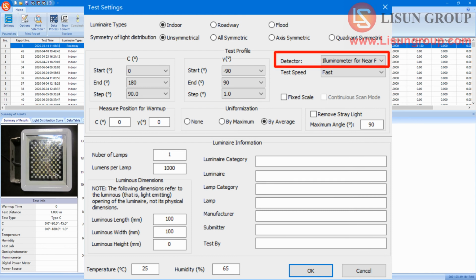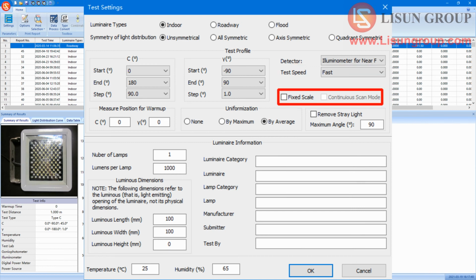Choose the correct photo detector that you use if you have more than one photo detector. Choose the test speed. Usually, normal speed can be used. Scale is not important. You can choose fixed scale. Input the angle to be monitored during the preheating. Usually just use the 0 degree position.